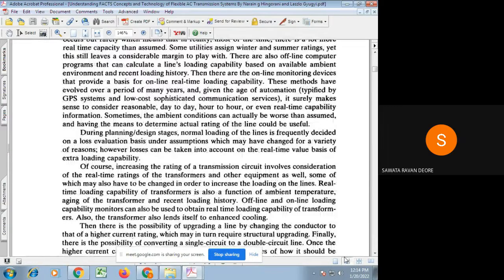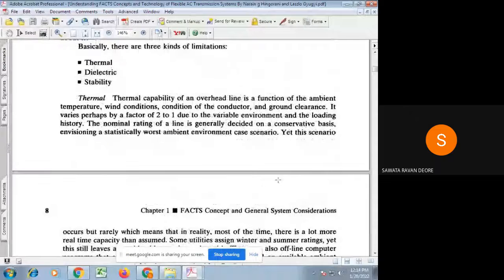Second one is the dielectric limitation. Second one is the dielectric rating. As I said, thermal rating is related to the current rating of a conductor. Similarly, dielectric rating is the voltage rating of the conductor, and that is decided by spacing between the conductors, ground clearance, and so on, as well as the ambient conditions.